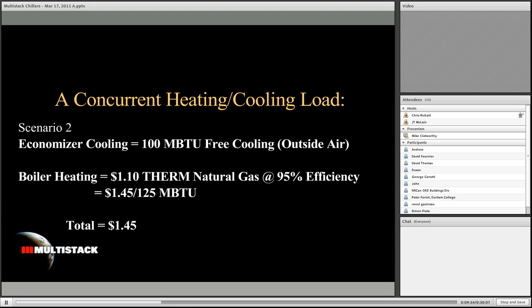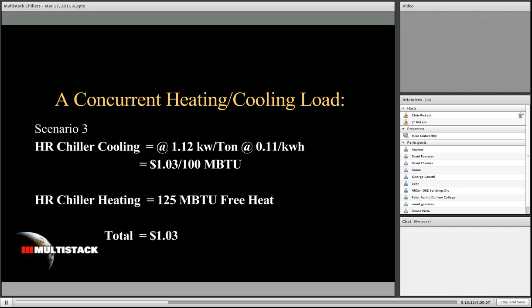economizer cooling. But for scenario two's purposes, let's just say that it truly is free. And let's make a comparison. So my therm of cooling is now completely free, but my boiler is still operating at 95% efficiency and at $1.10 per therm of natural gas. So in this scenario, my cost for a therm of concurrent heating and cooling capacity becomes $1.45. So it is in fact less expensive than scenario one, but it doesn't really tell the whole story.